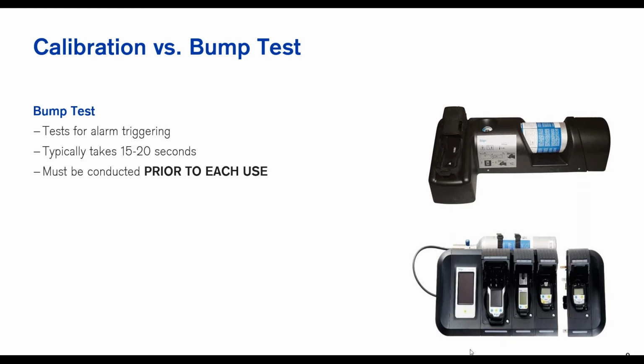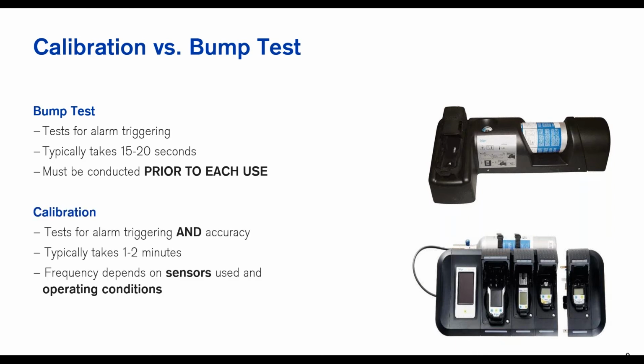So this is testing strictly for your alarm triggering. That's making sure that, okay, you're going to expose it to a certain gas with certain concentrations. You're just exposing it to that gas, a known concentration of that, and it's going to say, okay, I've got CO, my alarm's going to go off for carbon monoxide. I got H2S, my alarm's going to go off. It does not check accuracy. It simply checks to make sure that it is able to detect that particular gas. So typically it takes 15, 20 seconds. And then your next step, if your bump test fails, or depending on your meter, whatever model you have, it'll tell you the minimum amount of calibrations you should do. And so this full calibration is where you're actually going to check for not only your triggering, but also your accuracy, and it's going to help you correct that.